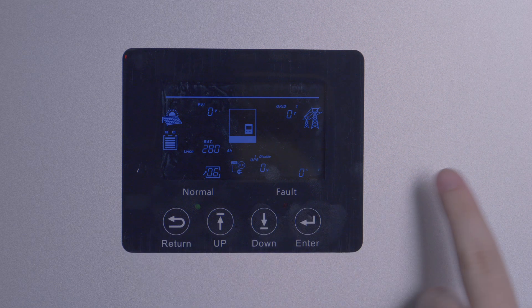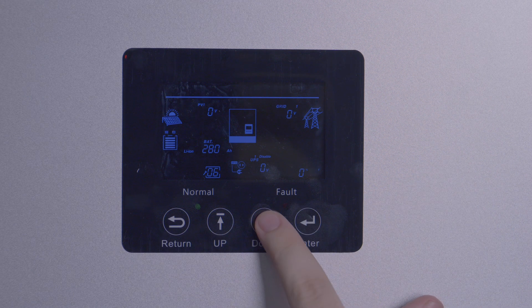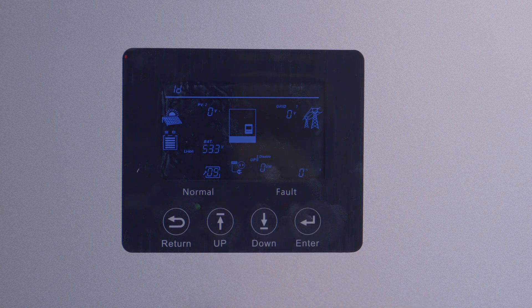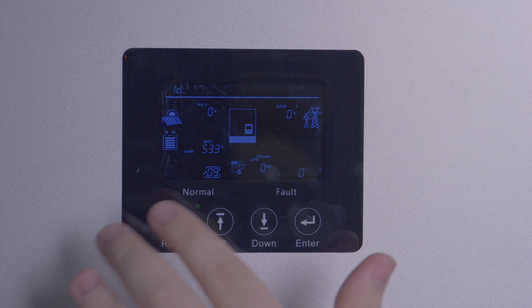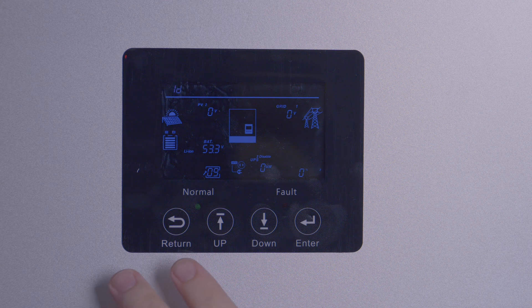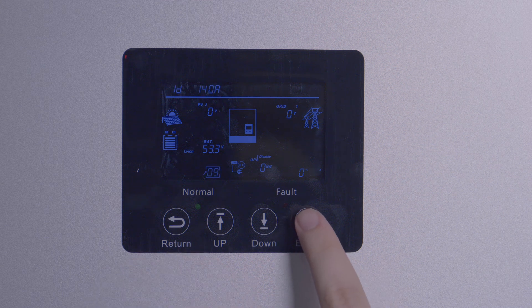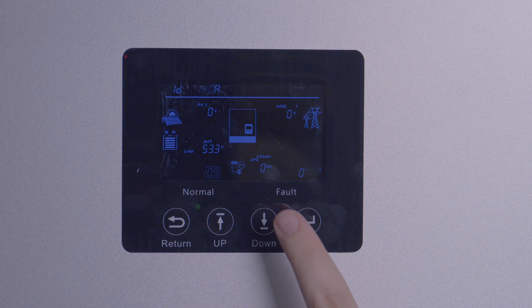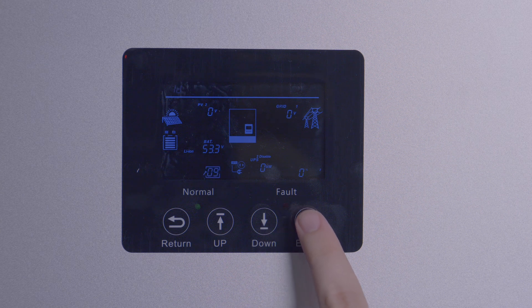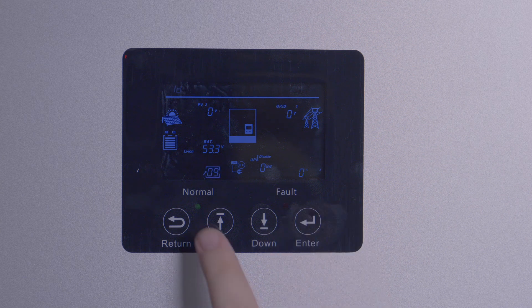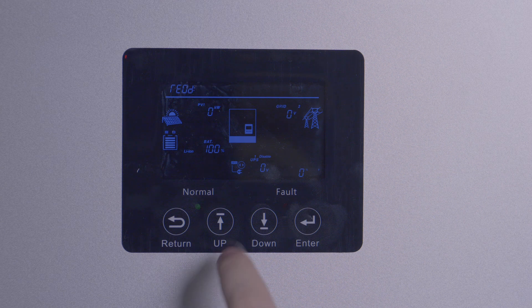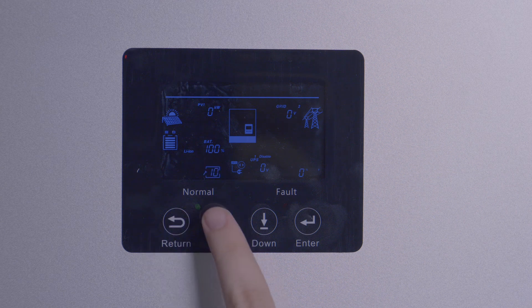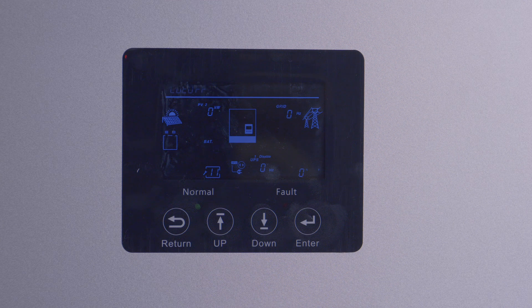Settings seven and eight are for adjusting voltage limits in lead acid mode only. Setting nine is the max discharge current — this is the max power your battery bank will output when it's in inverter mode. Setting ten allows you to change between voltage and state of charge control if you're in lithium mode. Setting eleven is the cutoff point for inverter power to switch to grid, which defaults to 15%, but can be raised if you want to switch to grid with more reserve energy in your battery bank.